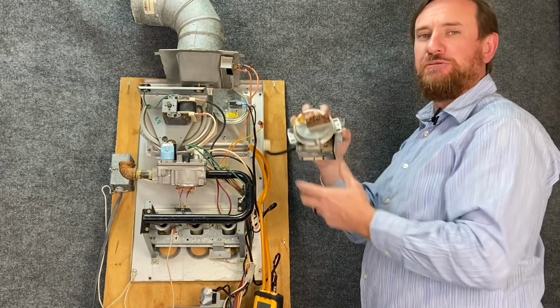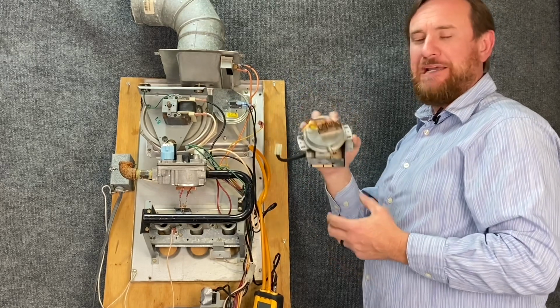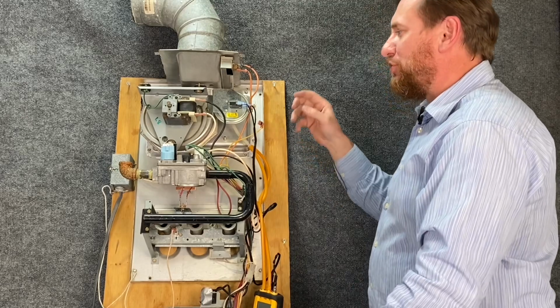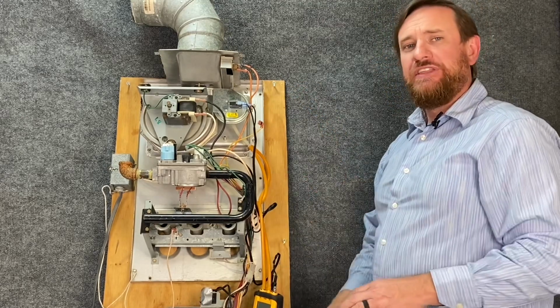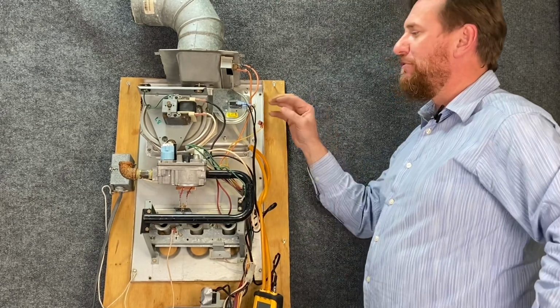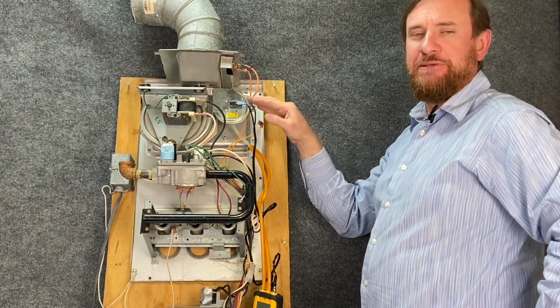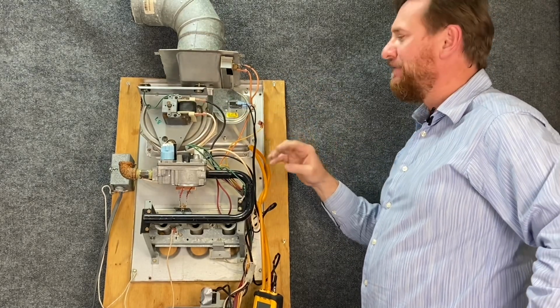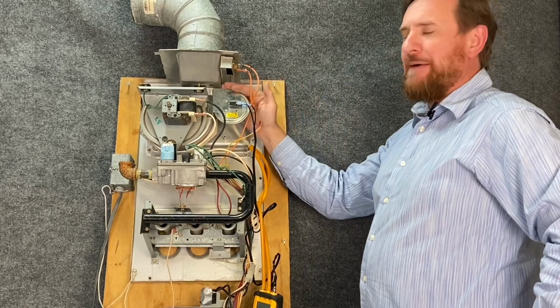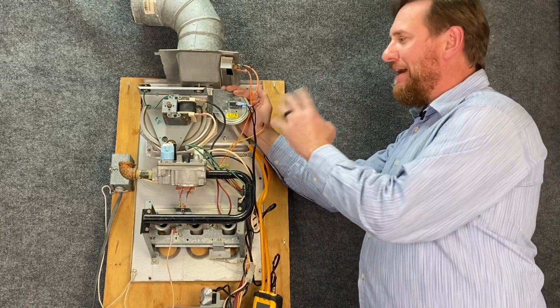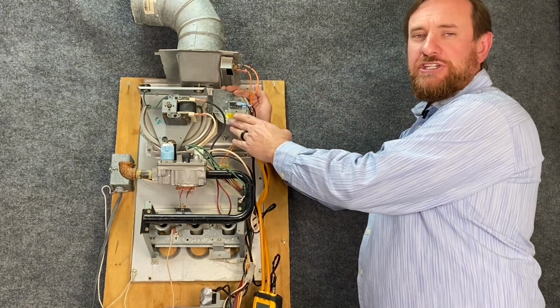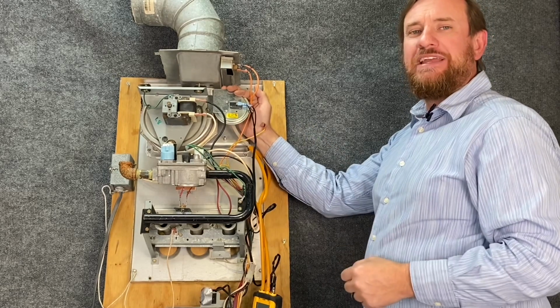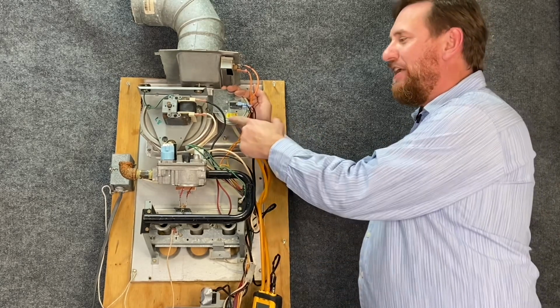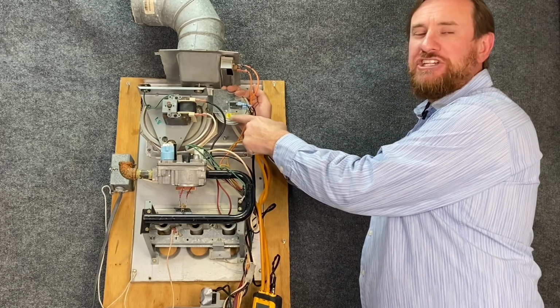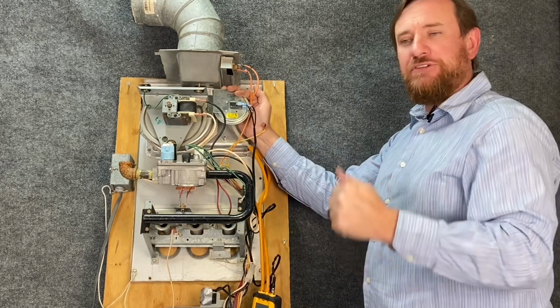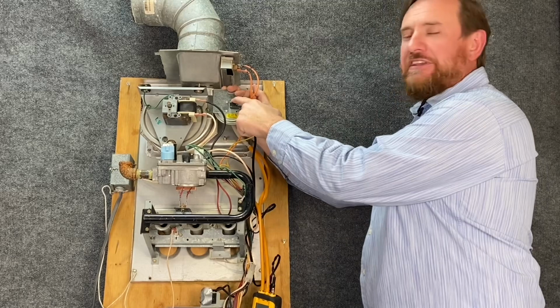Without a doubt, the control board would know that this switch hasn't been bypassed. I have seen people try to bypass these, and you never want to do that. At the end of this video, we're going to show you what happens if this motor is to fail and it was to be bypassed and how dangerous that can be. So you never want to bypass that. I prefer to always go back with the manufacturer's OEM pressure switch, but nowadays I hear that they do make a universal kit that you can adjust and change the springs to match exactly what's here. But if you use that, you must make sure that you put the exact amount of pressure.